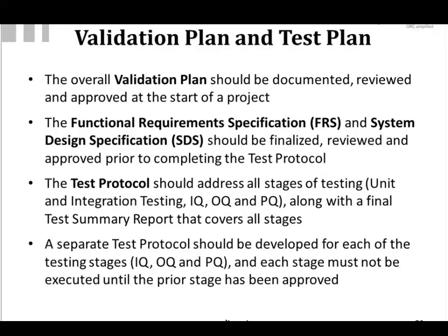And there should be a formal test summary report at the end that addresses each stage. Now, some people like to put a summary report out and a test protocol out for each individual stage, and that's fine. But you can also combine them where it's a very simple system or there's very little testing involved, and you want to combine them all into one package. Either way is acceptable as long as you cover each stage.